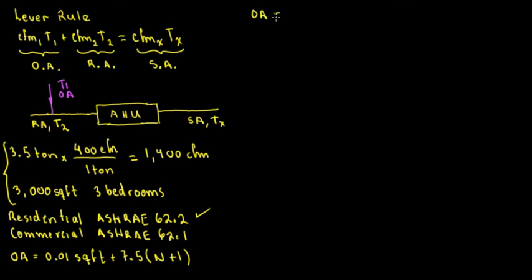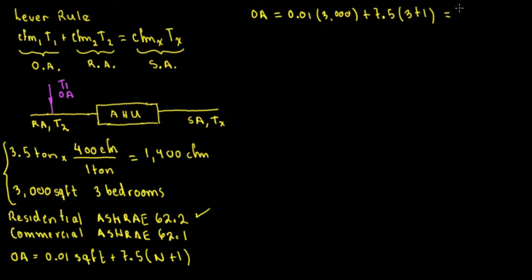Our outside air needed is: 0.01 × 3,000 sq ft + 7.5 × (3 bedrooms + 1). If we do the math, for this house the minimum required ventilation is 60 CFM. So the outside air is going to be 60 CFM.